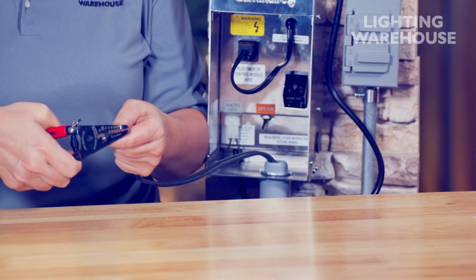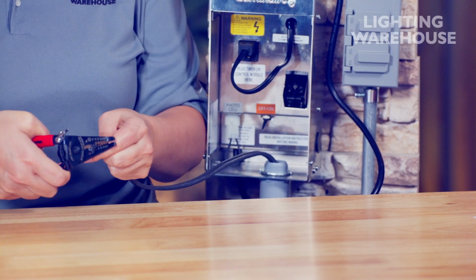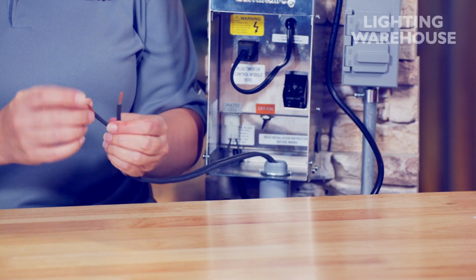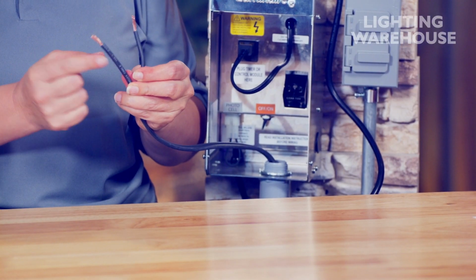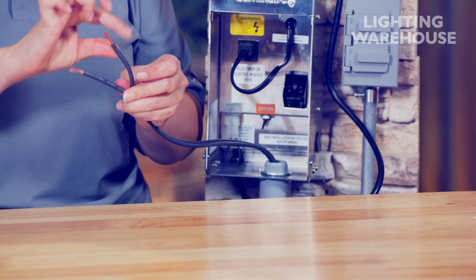Once you're ready to connect the transformer, split the cable down the middle and strip off about 1 inch to reveal the copper. Now with LED lights nowadays, it usually doesn't technically matter which is your common and which is the hot, but it's a good idea to get in the habit of treating the wire with the writing on it as the common and the blank wire as the lead. This is common practice in the industry and puts you in a good position should future technology have polarity requirements.